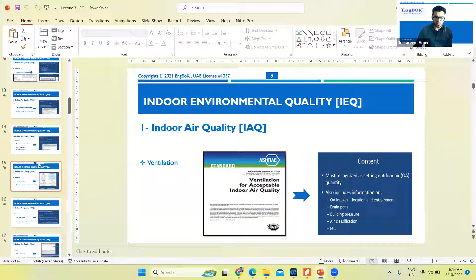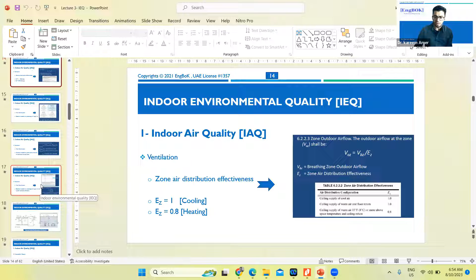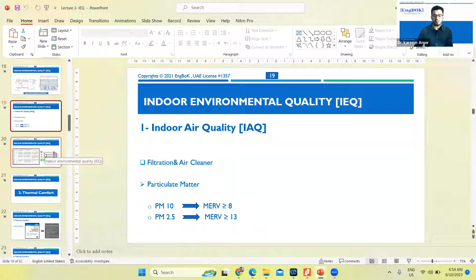For indoor air quality, we'll first have a quick overview about the types of ventilation, procedures, and calculations. Then we go in depth into calculating outdoor air requirements for people and area, and how to consider the effectiveness of air distribution based on heating or cooling from ceiling or floor, diversity, and ventilation efficiency. Then we cover filtration and PMs — what MERV rating is required for a filter in order to remove PM10 or PM2.5 micrometer particles as per standard requirements.